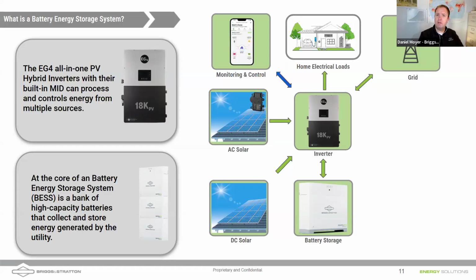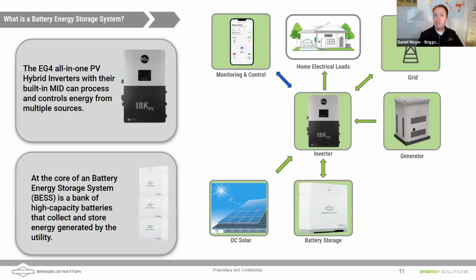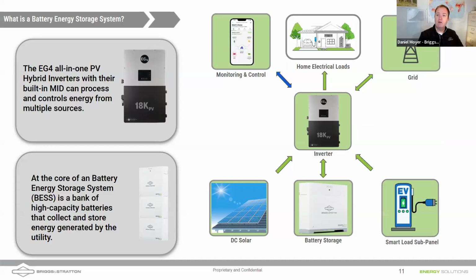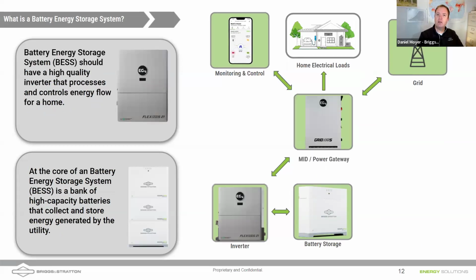Now, with the 18K PV, it just has that one third input, the gen input, right? We got our grid in, load out. Well, the grid could also be an out if we want to send back to grid. And then that gen port. The gen port really can only be used for one of three things. The AC coupled solar, like we're showing, we could bring a generator in using a 2-wire signal to start. We can start and stop that generator based on the state of charge of the battery. Or we can use it as a smart load output. So you kind of get either or. You can't get all three. That's where the GridBoss FlexBoss combination comes in together.